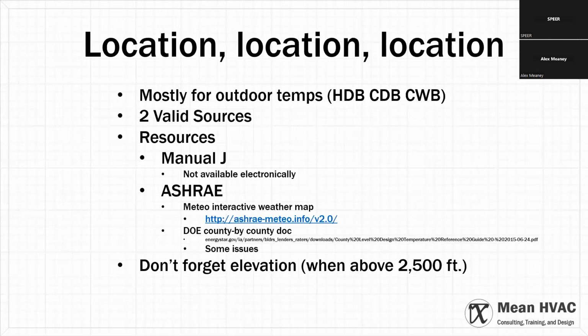And one last wrench in the works, if you will. You wouldn't perform a standard load calculation at these conditions, but if you wanted to use Manual J for sizing dehumidifiers, if you're going to size a dehumidifier for the needs of the building to maintain 50% relative humidity, you can do a load calculation at what are called peak dehumidification conditions. Pretty much the only place you're going to get those, they're not built into any software program that I know of. You have to override things to get there.